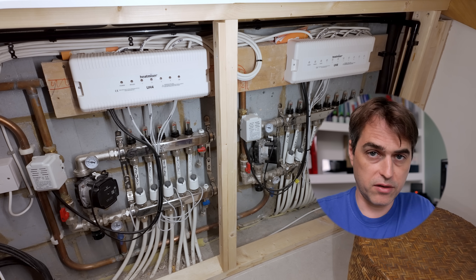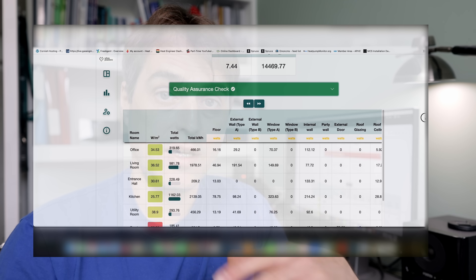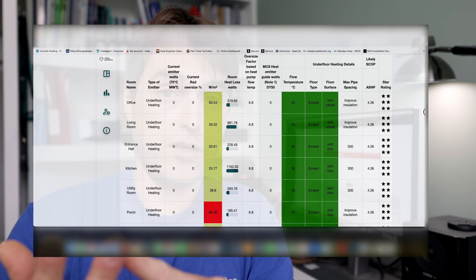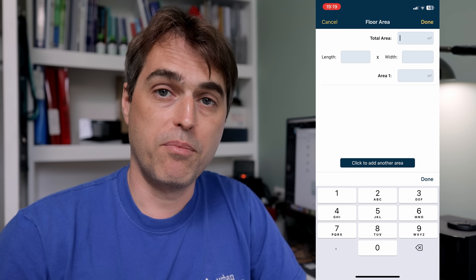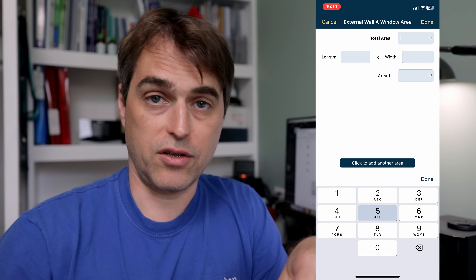Every heating design — regardless of the heat source, whether boilers or heat pumps — starts with heat loss calculations. This is what everything else will be built upon. You need to learn how to correctly do the heat loss calculations and also how to interpret that data. Based on heat loss, you're going to size your heat pump, size your emitters, design your underfloor heating, and size your pipework. Get the heat loss wrong and all of those items will be wrong as well. I use Heat Engineer software for heat loss — you measure the property, type information into the app on your phone, it sends that to the cloud, then you finalize calculations on the desktop.